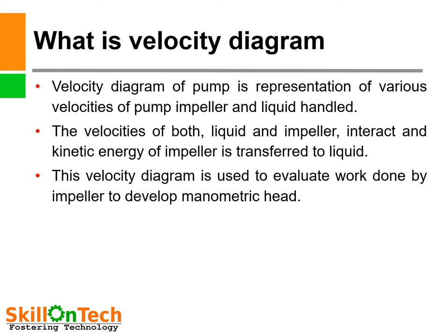What is a velocity diagram? As we know, when liquid enters into a centrifugal pump impeller it has two velocities — one is the velocity of the liquid and the other is the velocity of the impeller. So those velocities are represented by velocity diagrams. The velocity diagram of a pump is a representation of various velocities of the pump impeller and liquid handled. The velocities of both liquid and impeller interact, and kinetic energy of the impeller is transferred to the liquid. This velocity diagram is used to evaluate the work done by the impeller to develop manometric head to the liquid.